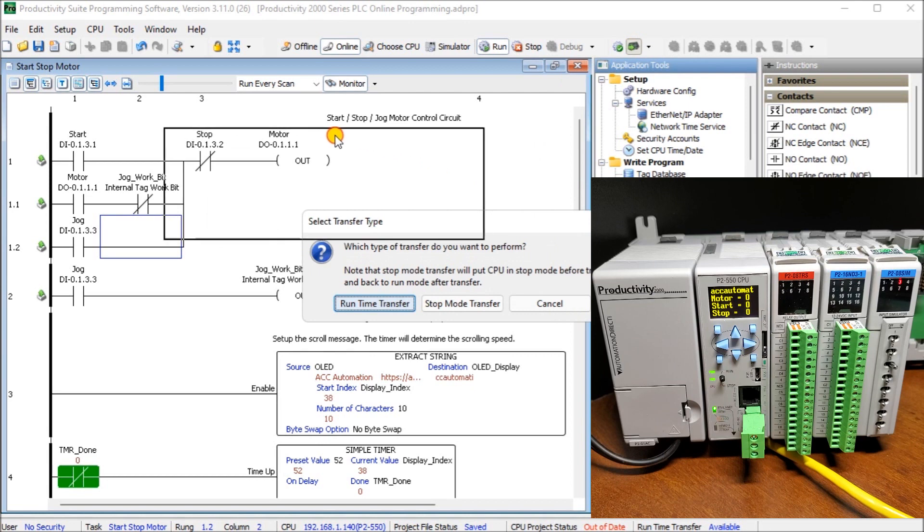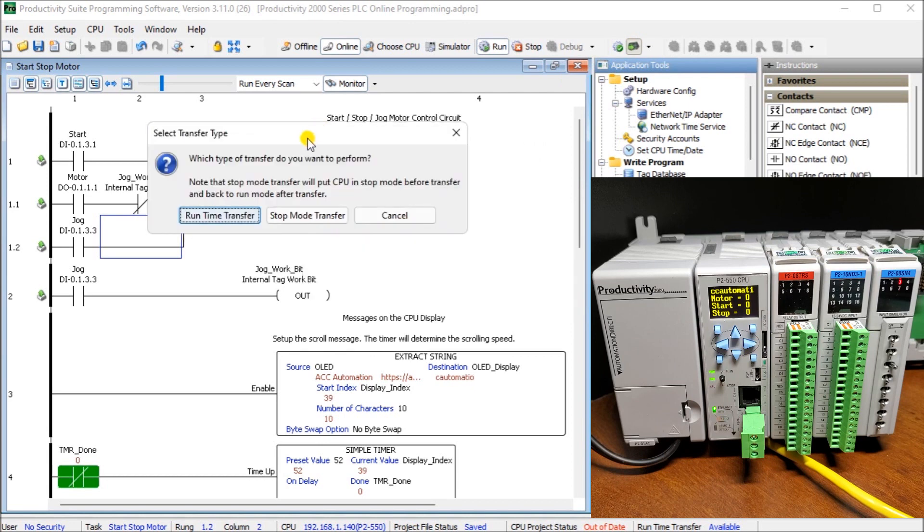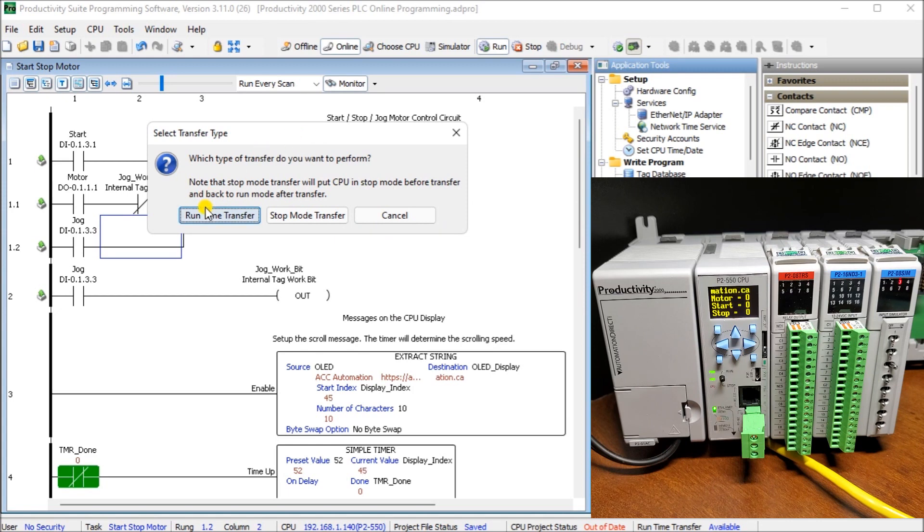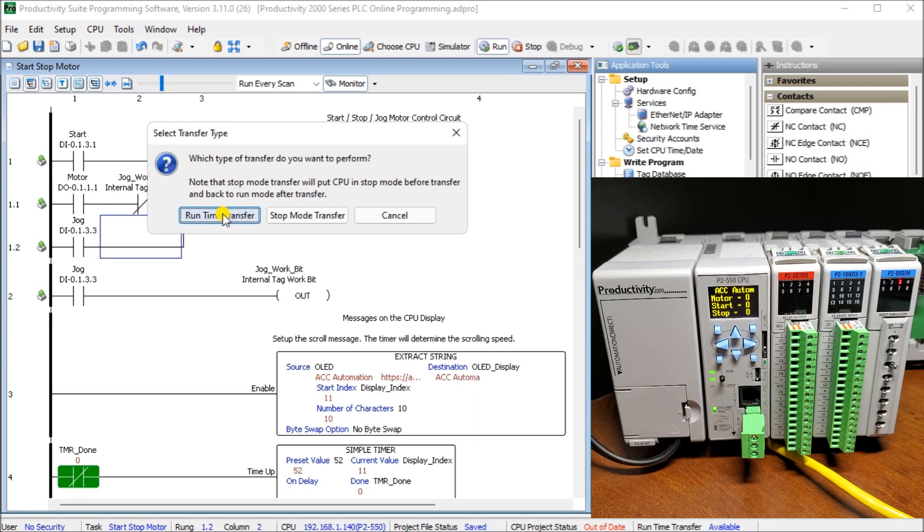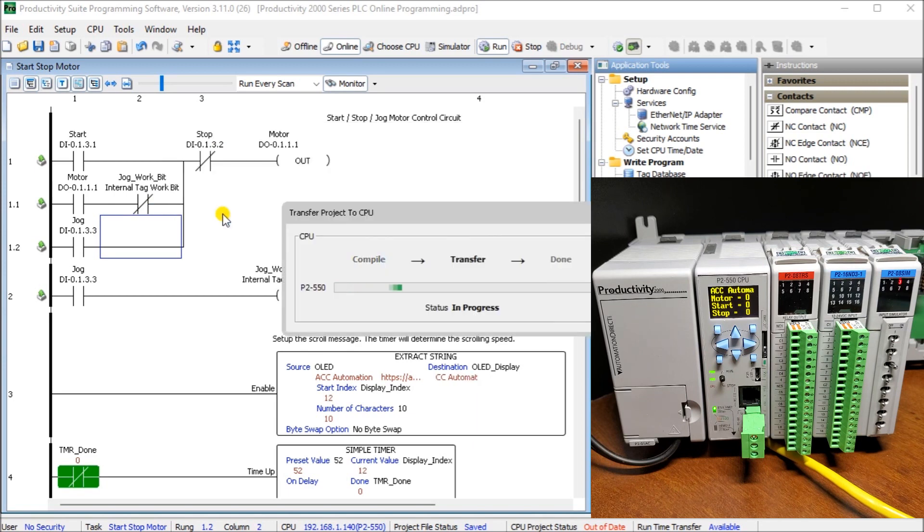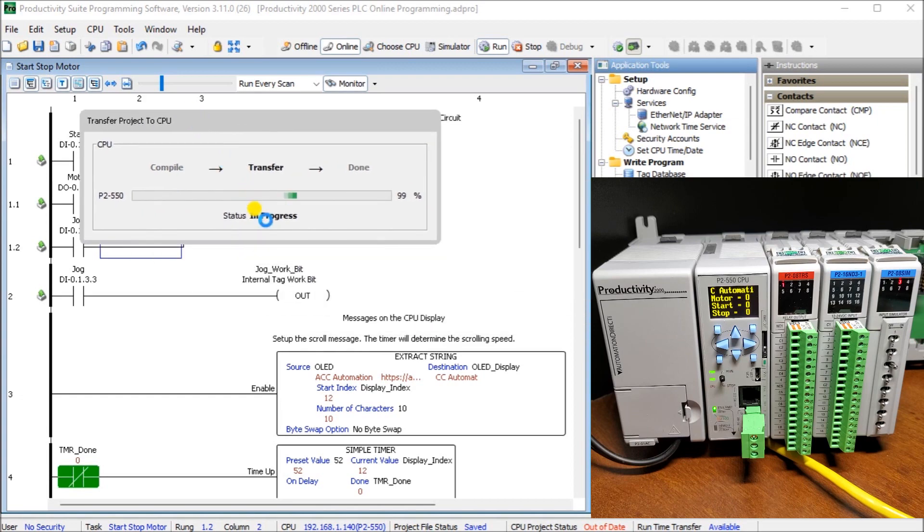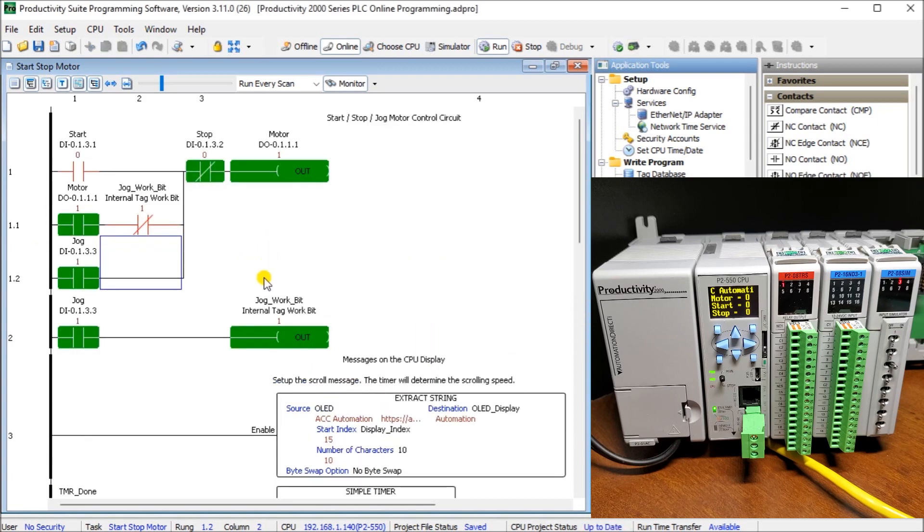Here it's asking me what type of transfer do we actually want and we have two choices. We have the runtime transfer which is what we're going to be doing, that's the online programming itself, or we have the stop mode transfer which actually takes your PLC into program mode, transfers the program, and then allows you to start the program once again. So we're going to do the runtime transfer. It will then transfer that over.